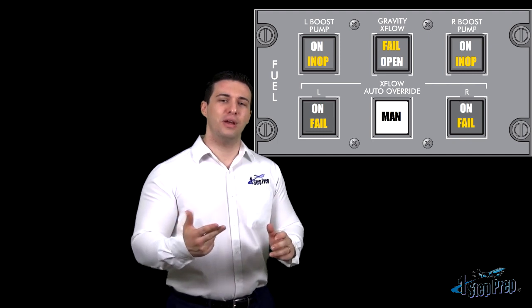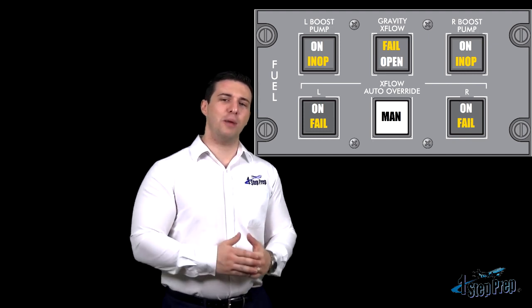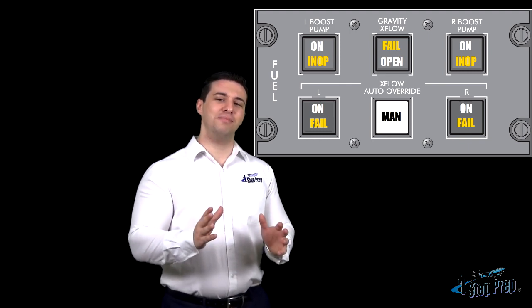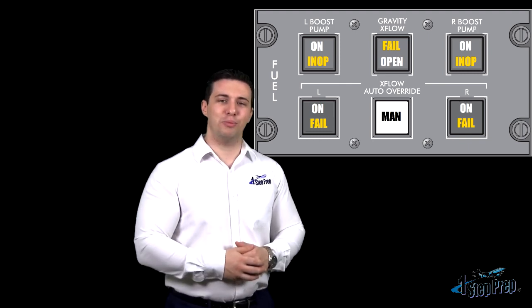How does the aircraft know the pump is inoperative? Low pressure. You have a pressure sensor there, so essentially that pressure sensor is not sensing pressure, indicating you have a low pressure indication.